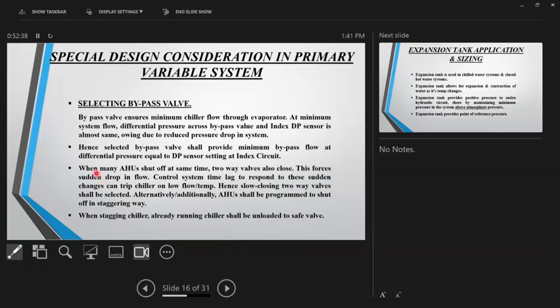For primary variable systems, when many AHUs shut off at the same time, two-way valves also close very, very fast. I mean, let's say there are 100 AHUs, and through the BMS you shut them all at one time. Then their valves also switch off at the same time. Now the flow immediately reduces. If the valve closes, the flow immediately reduces. But the control system actually takes time to understand. There is always this system lag.